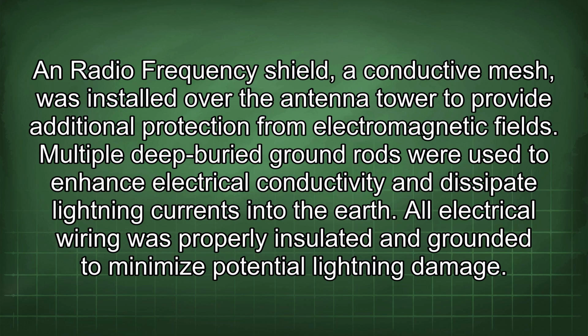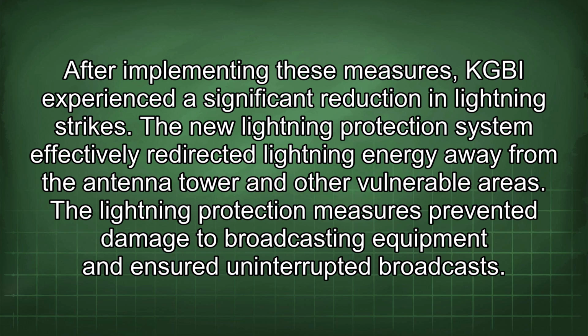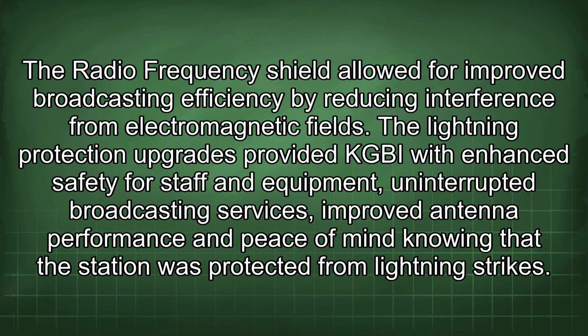All electrical wiring was properly insulated and grounded to minimize potential lightning damage. After implementing these measures, KGBI experienced a significant reduction in lightning strikes. The new lightning protection system effectively redirected lightning energy away from the antenna tower and other vulnerable areas. The lightning protection measures prevented damage to broadcasting equipment and ensured uninterrupted broadcasts. The radio frequency shield allowed for improved broadcasting efficiency by reducing interference from electromagnetic fields.